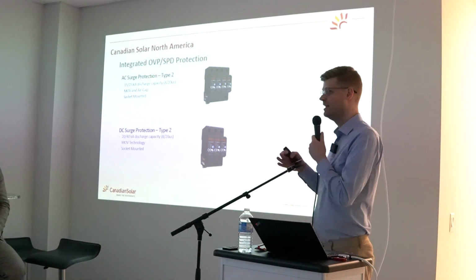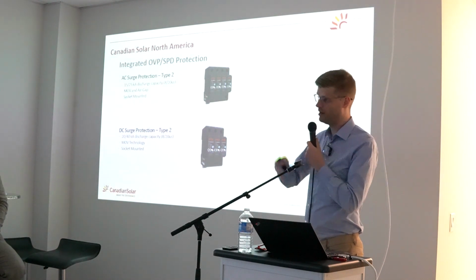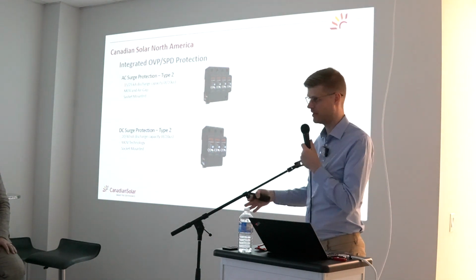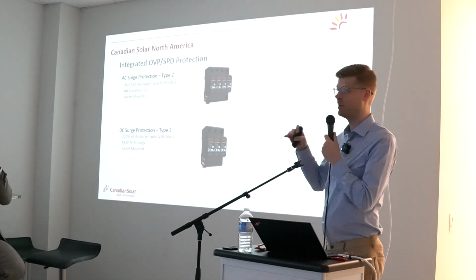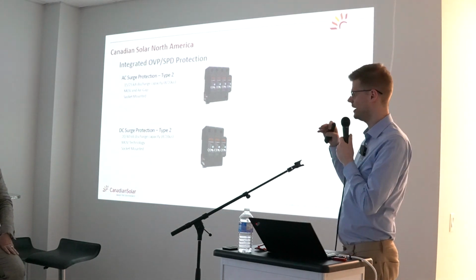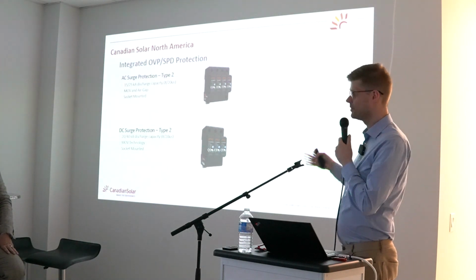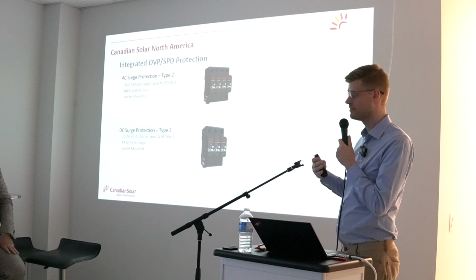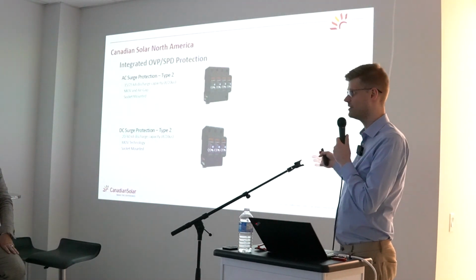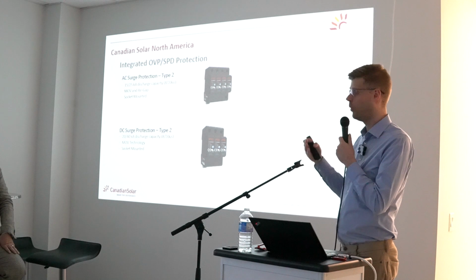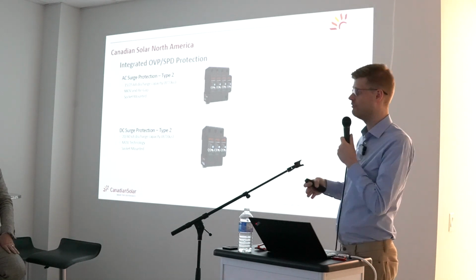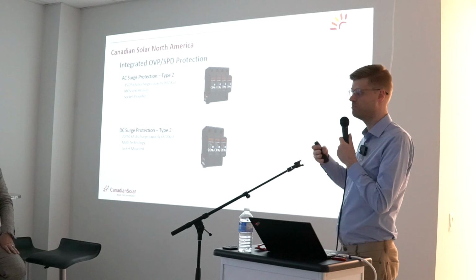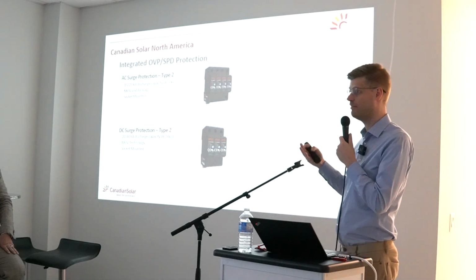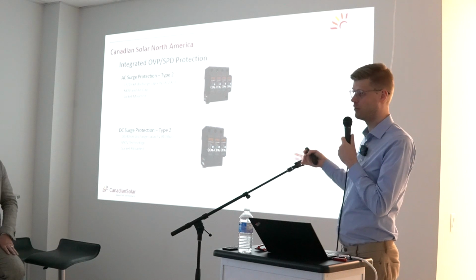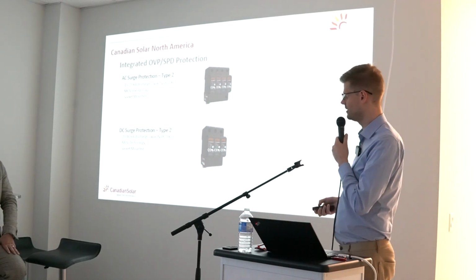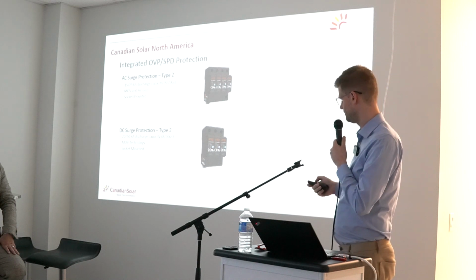That is important because compared to old systems in the past where you had a combiner box and you had pretty much, let's say, 20 strings in, one combined output, you only had one DC overvoltage protector built into the combiner box. Now with these new systems, you have multiple strings separated from each other, landed directly at the inverter. So there is not a single location anymore where you could put an additional overvoltage protector. If it would not be integrated into the inverter, it would be not possible to add, or not economically feasible at least, to put additional overvoltage protectors in the system.